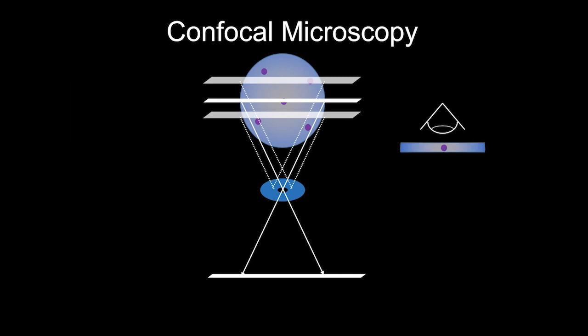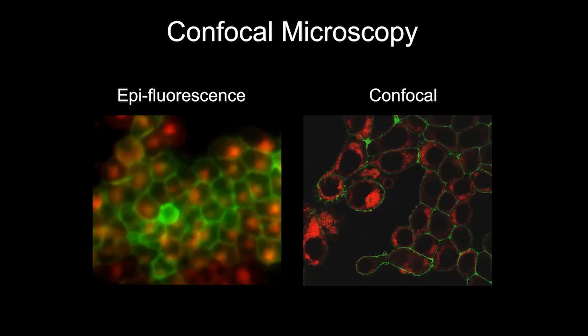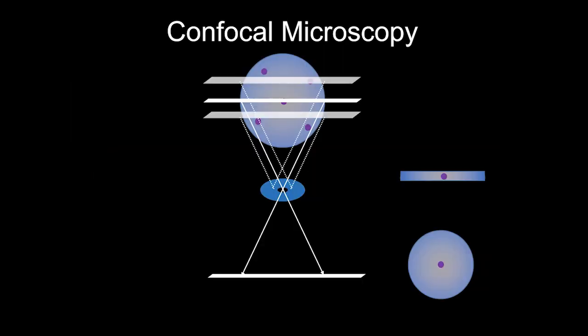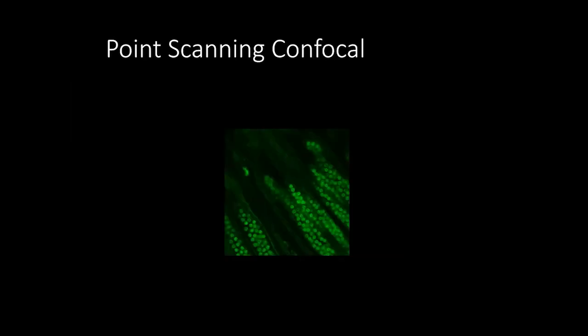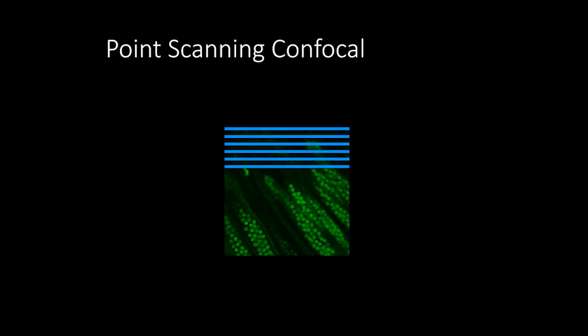Confocal microscopy gives you images like this — you can clearly see the green is on the plasma membrane and the red is peri-nuclear. Most of the confocal scanners in the facility are point-scanning confocals: since light comes through only one spot, a single detector images the sample line by line, point by point, like an inkjet printer.